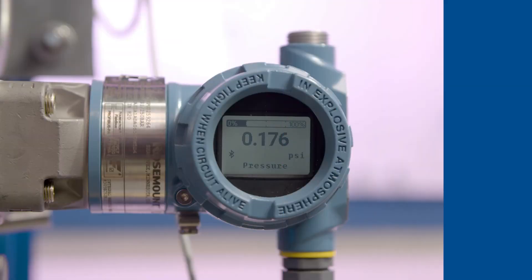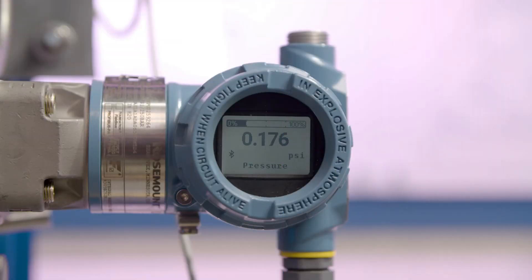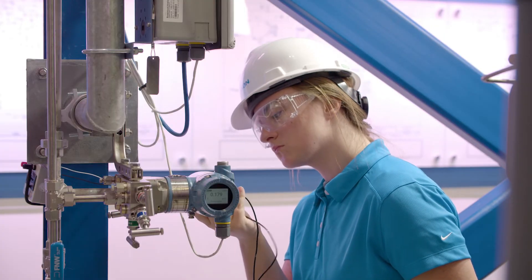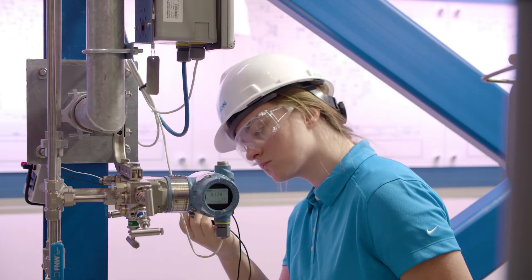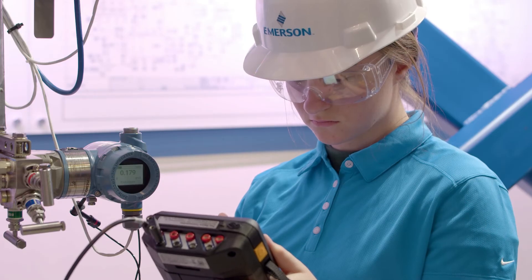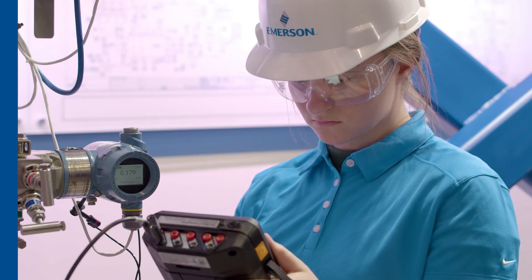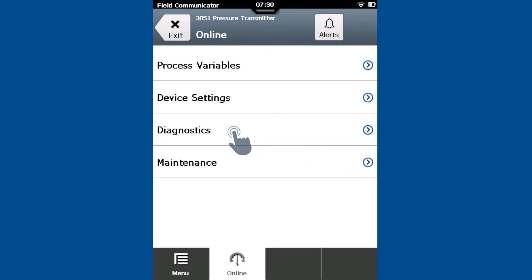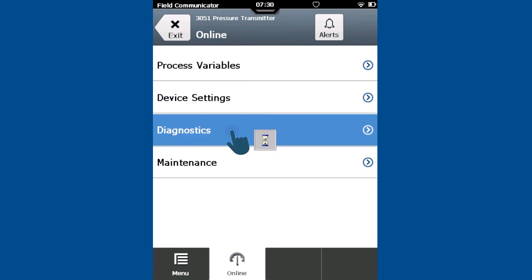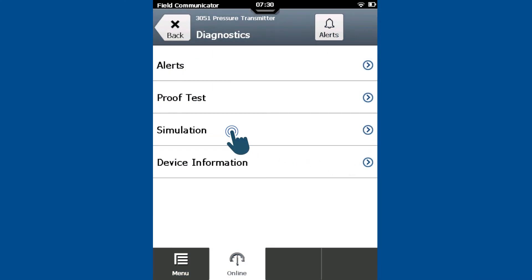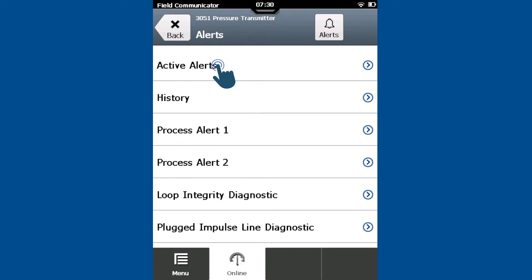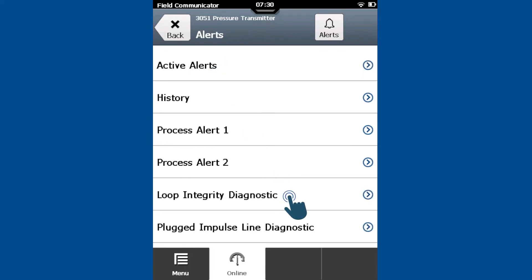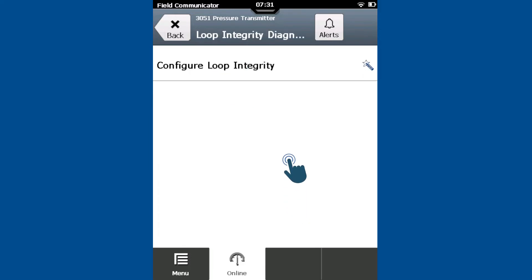Install the transmitter prior to Loop Integrity configuration. Once installed and connected, navigate to the Diagnostics menu. Select Alerts, then select Loop Integrity Diagnostic and start the Configure Loop Integrity method.